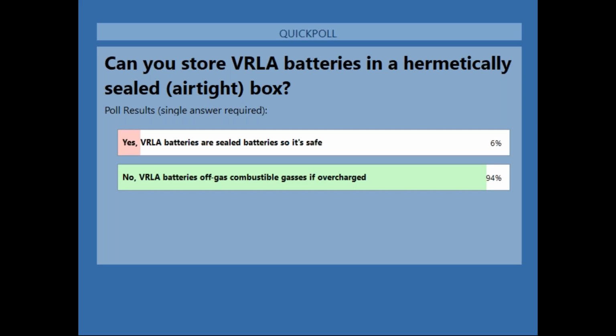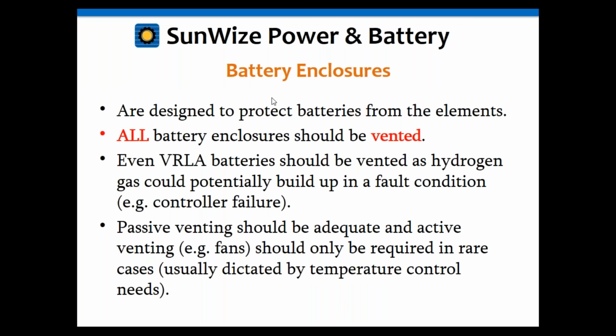Yeah, you definitely don't ever want to put valve-regulated batteries in sealed enclosures. What can happen is if those were to gas for any reason, the charge controller should fail, something should happen. If they gas at all, you could get a buildup of hydrogen and you could have an explosive situation. It's very rare, but it can happen, and when it does, it's incredibly dangerous. So as an engineer, you always want to design for a worst case scenario. Because of that, you always have to have ventilation of some form.